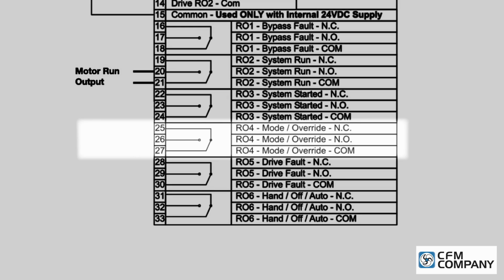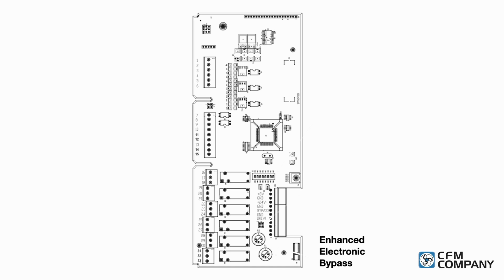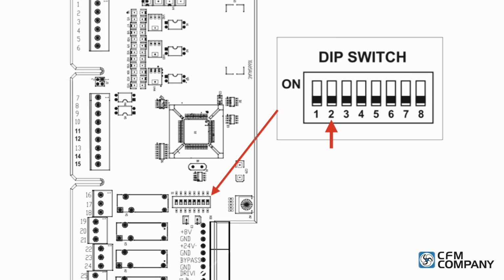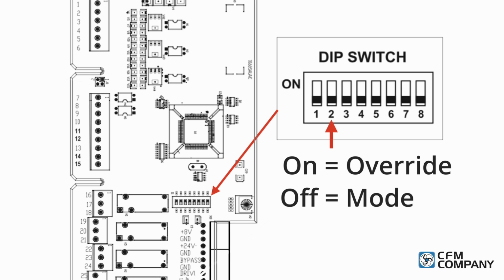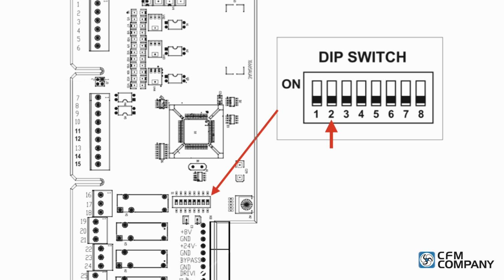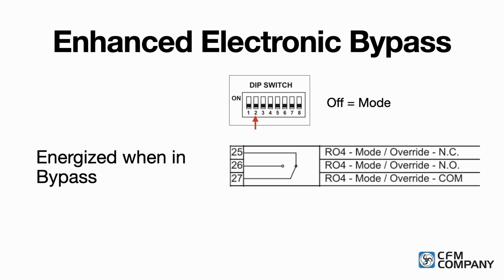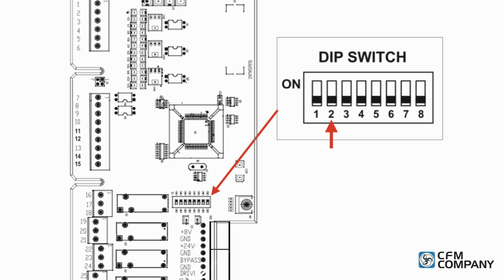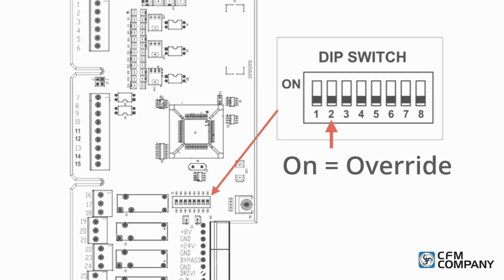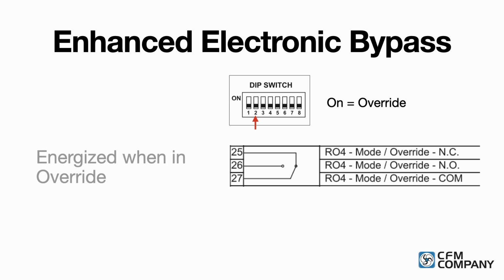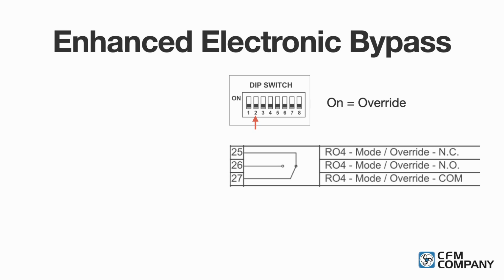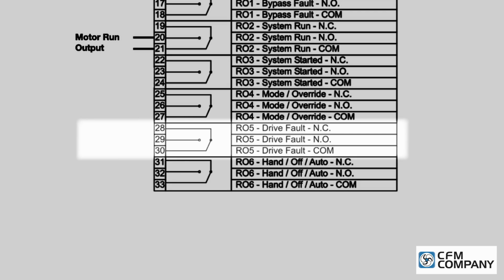Relay 4, terminals 25, 26, and 27 is the mode override relay. Its function is configured with the dip switch number 2. Off equals mode, on equals override. If relay 4 is configured for mode, dip 2 is off, default. The relay is energized when in bypass and de-energized when in drive. If relay 4 is configured for override, dip 2 is on, the relay is energized when in override and de-energized in all other modes.